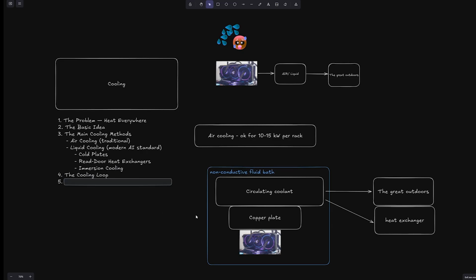The cooling loop has 4 different steps. Inside of the loop, water carries heat from chips to a plate radiator, onto the heat exchanger, where heat is transferred to an outside loop. Then outside of the loop, chillers, dry coolers, cooling towers, etc. release the heat to the environment, and lastly, pumps keep everything flowing at a few gallons per minute per rack. There are different cooling options depending on the climate.